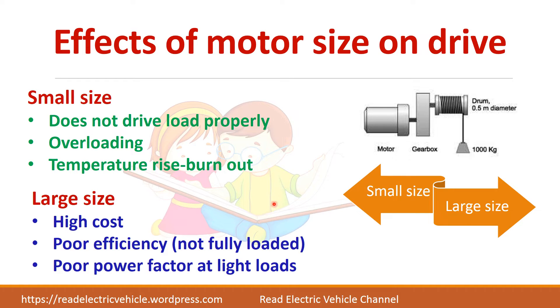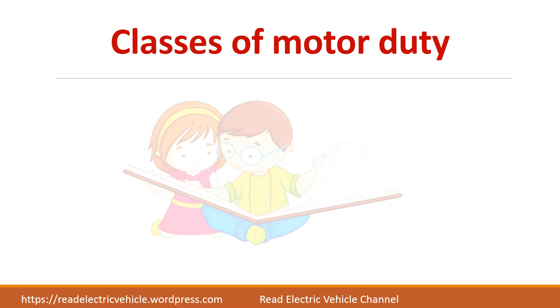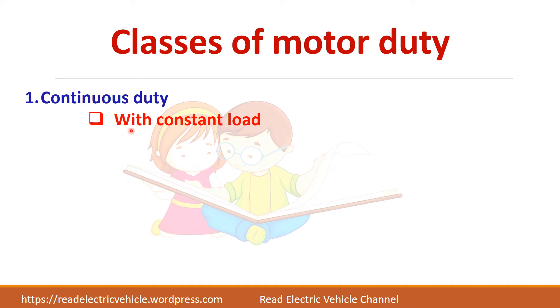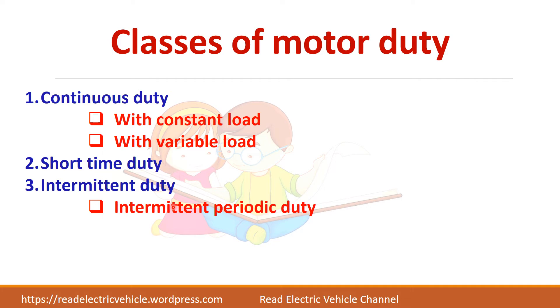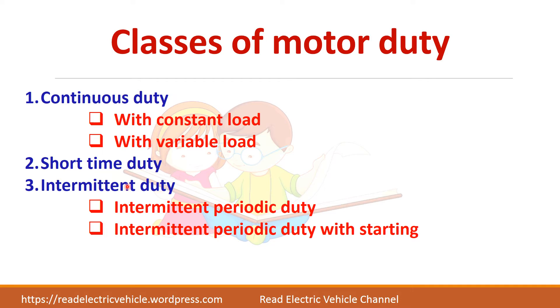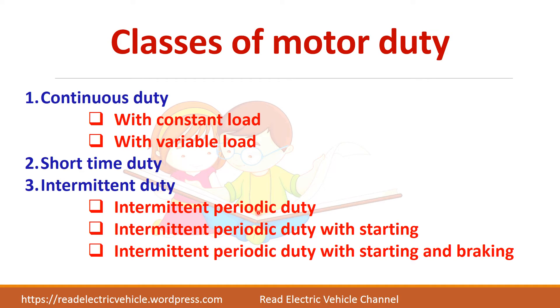All these factors are to be considered before choosing the motor for a drive. What are the different classes of motor duty? First, you have continuous duty. Then you have short time duty, and the third one is intermittent duty. In continuous duty, there are two cases: if the load is constant or if the load is variable. In intermittent duty, you have periodic duty where the load repeats periodically, and whether you have to consider the starting period and braking period. The major classifications are three types: continuous duty, short time duty, and intermittent duty.